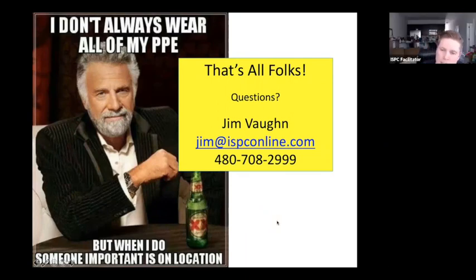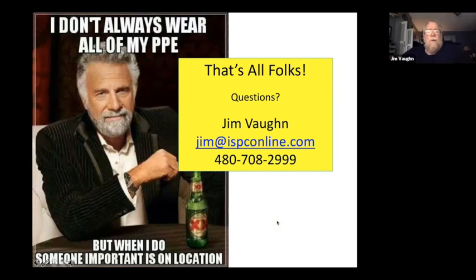Okay. One last question. Do the TOV numbers always refer to phase voltage? Not always, because your exposure usually is only phase to ground, because you're well away from the other phase in transmission. But what you will see on the tables in OSHA is phase to ground and phase to phase. But remember the graphic that I showed you. If you are working with tools that can go into the MAD of both, then you have to consider phase to phase. But in most all applications, if we work in our conventional work methods, our only exposure is phase to ground. And if you look at the alternative table that OSHA provides for TOV, the alternative table is calculated at a per unit of 3, which is like 3 times. And you'll find that the MAD for 500 kV at a TOV of 3 is like 23 feet. There's no way that you could work or even climb a structure in that case.